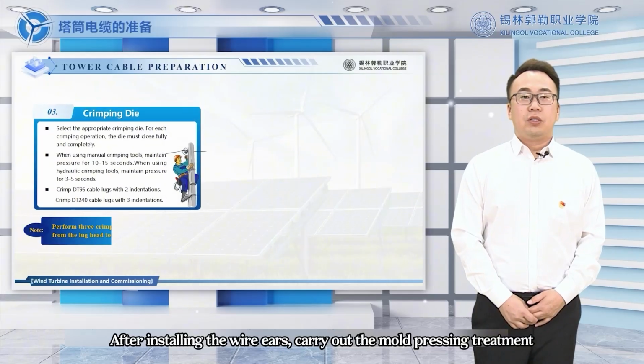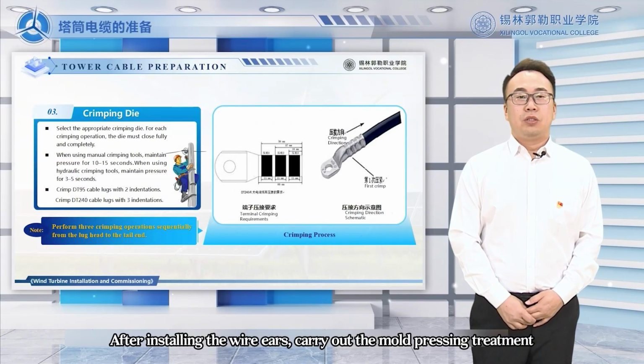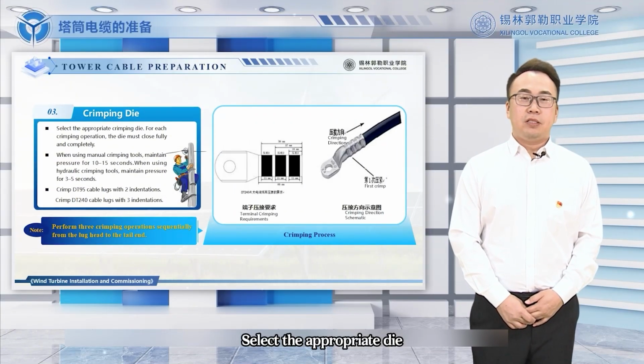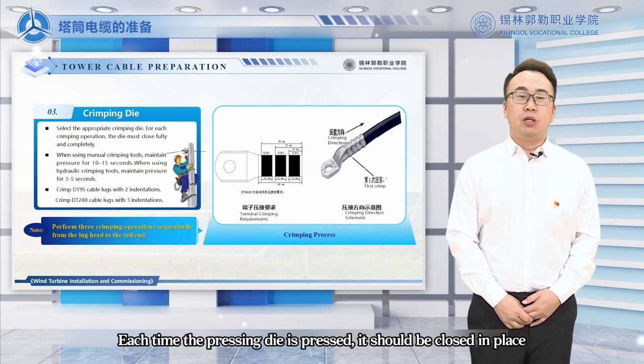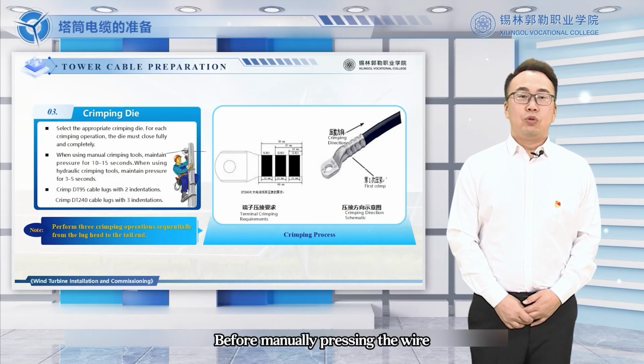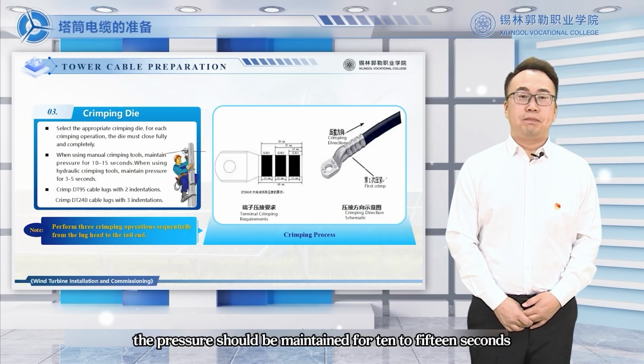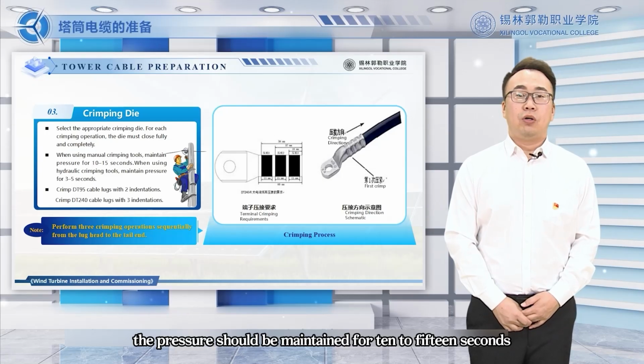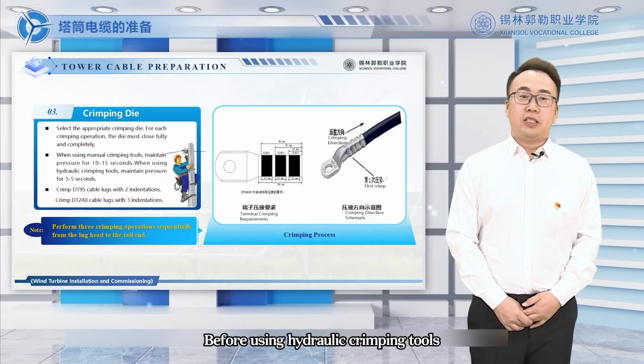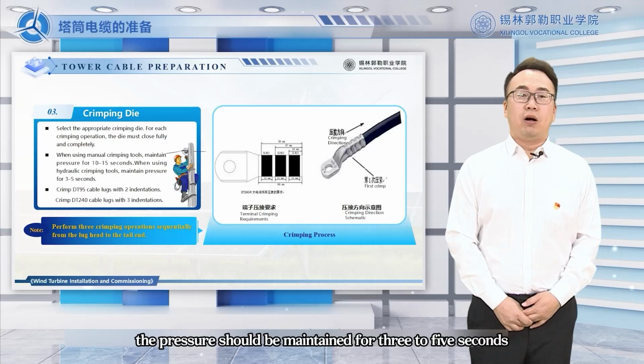After installing the wire ears, carry out the mold pressing treatment. Select the appropriate die, and each time the pressing die is pressed, it should be closed in place. Before manually pressing the wire, the pressure should be maintained for 10 to 15 seconds; when using a hydraulic crimping tool, the pressure should be maintained for 3 to 5 seconds.